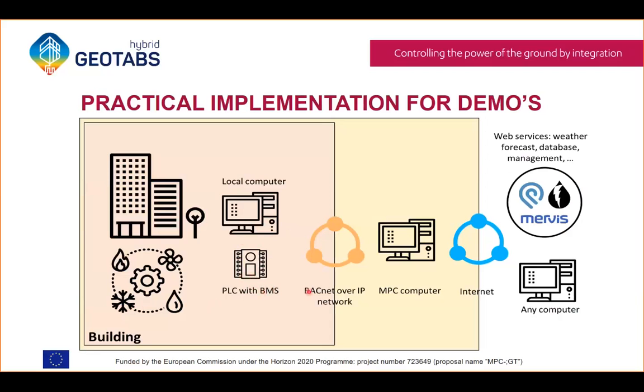We then added in this building a computer connected to the same network as the PLC, and we were able to send our control actions and read the measurements using the BACnet over IP protocol, which was supported by this PLC. We also ensured that we had an internet connection to get weather forecasts, send measurement data to a database, and get remote access to this computer. The MPC was then running on this computer and controlling the building.